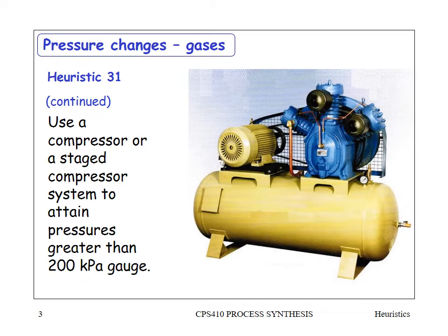Continuing with heuristic 31: use a compressor or a staged compressor system to attain pressures greater than 200 kPa gauge. What's shown is an air compressor — normally air compressors compress to about 800 kPa and therefore you need a staged compressor. The one shown is belt-driven with a three-stage compressor.